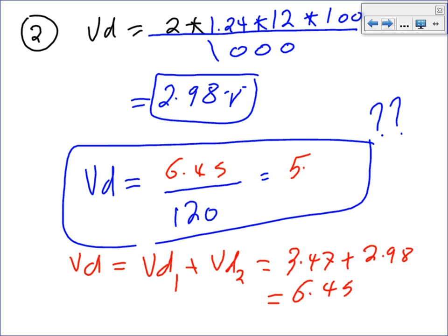5.3%. No good. Can you guys see why? Because we lost a lot of voltage from the 120, 5.3%. What does that mean? We exceeded the voltage drop limit at this point. What do we need to do? Up the wire size. We know we have a problem right now, but let's just find the voltage drop for all of them. Okay, any questions, guys?